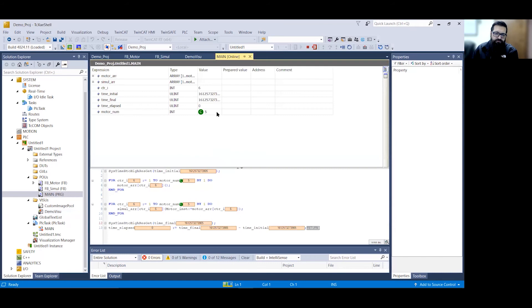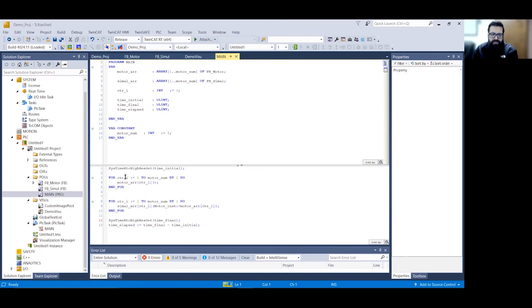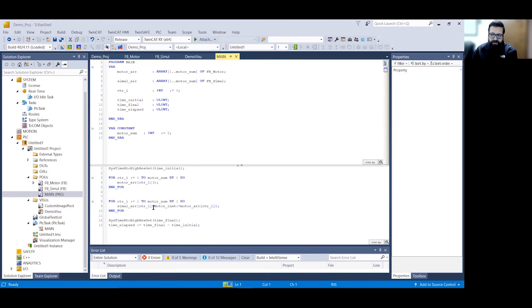The reason this works cleanly by just changing one constant from three to five is because I have for loops down here. The for loops iterate over the array element by element. On the first pass, the counter equals one, and it accesses the first element of the motor array. Each iteration increments the counter, going through each element until it reaches motor_numb — currently five. This approach is trivial when going from three to five, but if you imagine scaling from 10 to 20 or 50 to 100, this kind of approach to PLC programming is really powerful and cuts down on production time.